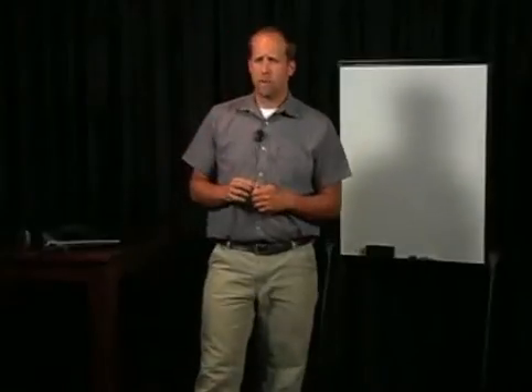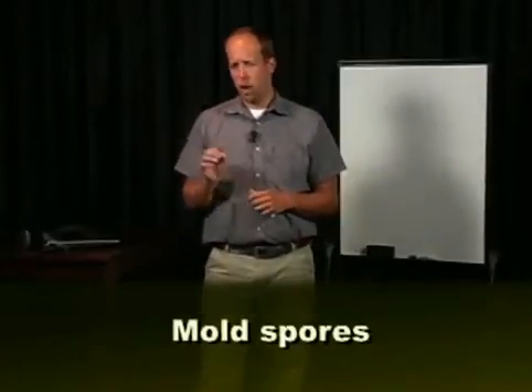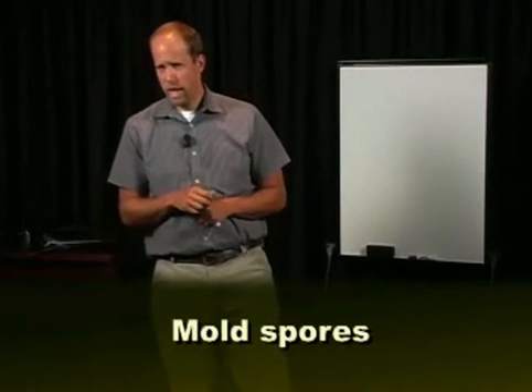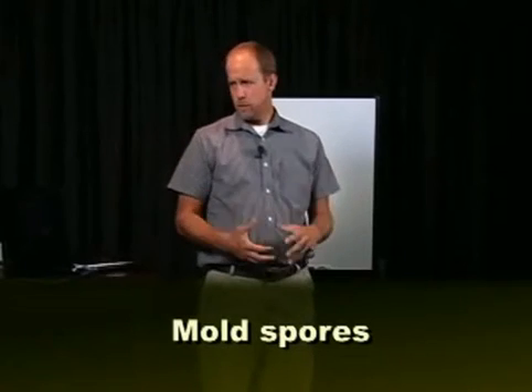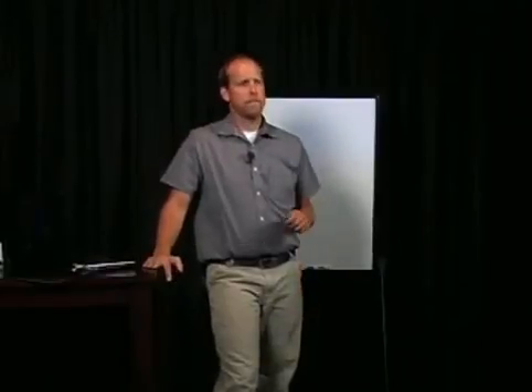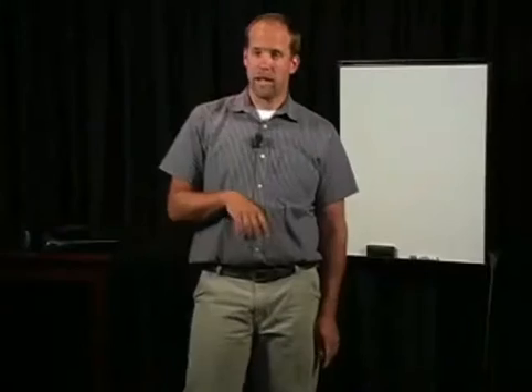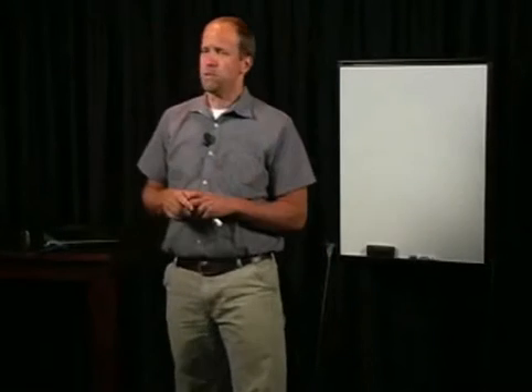Spores are almost always present in outdoor and indoor air, and almost all commonly used construction materials and furnishings can provide nutrients to support mold growth. It's not possible to prevent mold from entering the interior of a building. How about temperature? Well, human comfort constraints limit the use of temperature control. Air temperature inside a building that is suitable for occupants is also good for mold growth. Most buildings are kept between 65 and 75 degrees Fahrenheit. This temperature range is suitable for mold growth. Some fungi can thrive in temperatures as cold as 15 degrees and some as hot as 122 degrees.